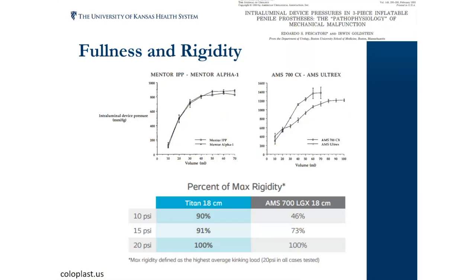Looking at the curves above, you can see that the Coloplast on the left and the Ultrex on the right is more of a flat line, requiring a lot more to be pumped in to get to that rigidity. The question you may be asking is how many people don't pump it all the way up? And we recognize that a significant amount of people aren't able to get the device 100% inflated. So this can come into play when people can only get it to about 15 psi.